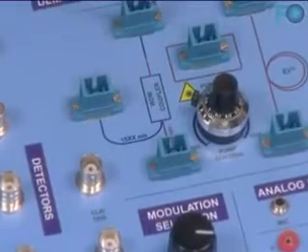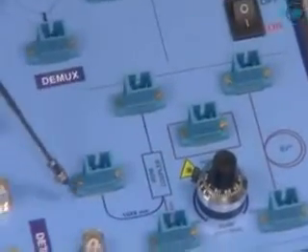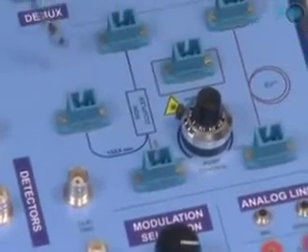The EDFA given is modular in nature for its complete understanding. One can assemble the EDFA from its basic components provided on the backplane of Light Runner. The list of experiments possible on EDFA here ranges from forward and backward pumping, optical gain variation, single and multi-wavelength amplification, etc. I can see these mux and demux are the ones which we are installing in the field, so it will be interesting for me to train my engineers for the field.